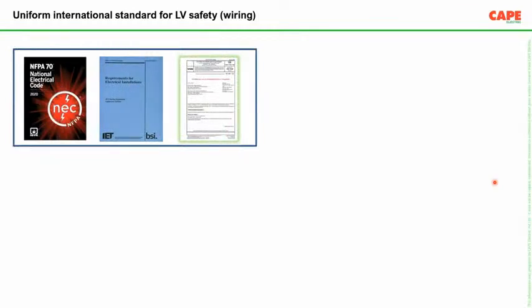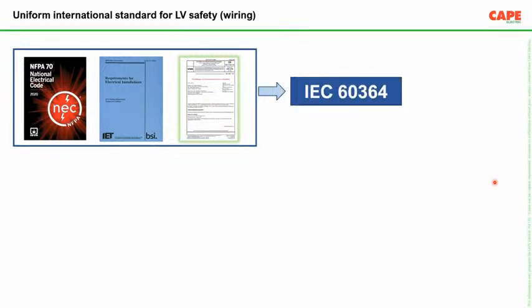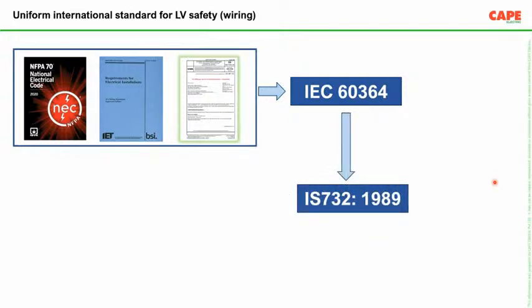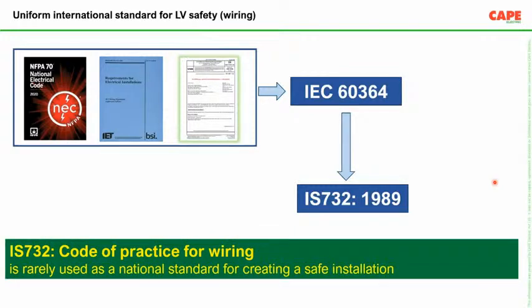Now, as I showed you, the uniform international standard for low voltage safety is IEC 60364. Worldwide, all the countries follow the same rules stipulated by IEC 60364. In India, we have the equivalent, which is called IS 732, Code of Practice for Electrical Wiring. In 1989 itself, not today, 31 years back, the Bureau of Indian Standards adopted the standard IEC 60364, and it has been made as the Code of Practice for Electrical Wiring. Lot of engineers know the code number, but what is written in the code is not followed very well.